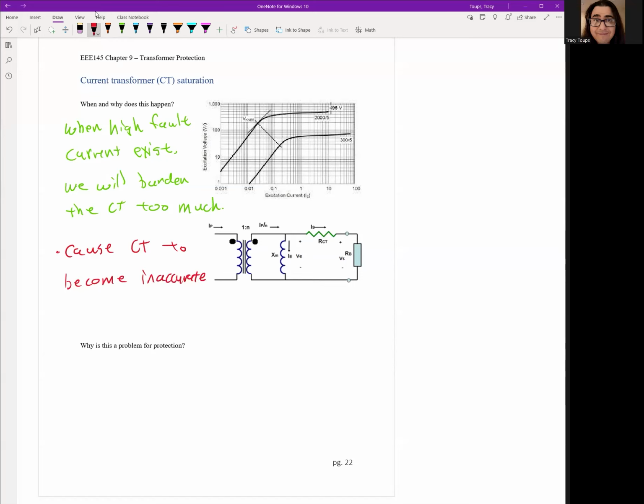Okay. So basically, this is called a knee curve. We're not going to go into too much detail, but down here is the linear region, and you can operate here normally, and everything's fine. This is fine right in this region, all of here, pretty much. Anytime you get to the flatter side, this is the saturation region. You don't want to operate here. This is bad. Anytime it's this flatter area, so probably about right here, we start entering saturation. This is bad. Don't be here.